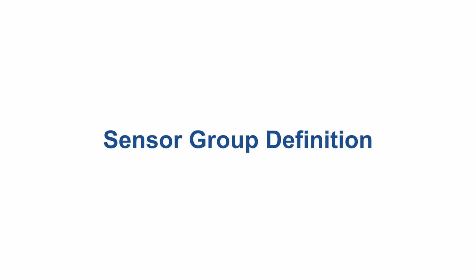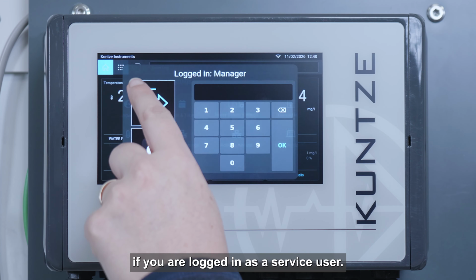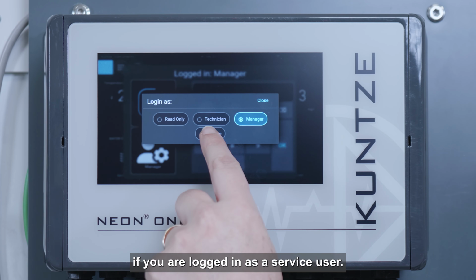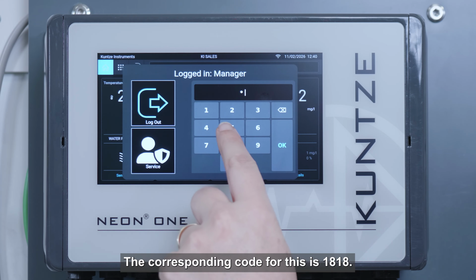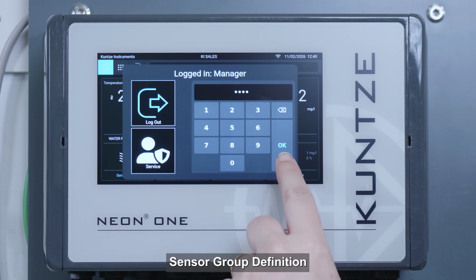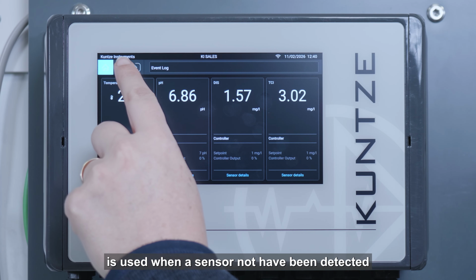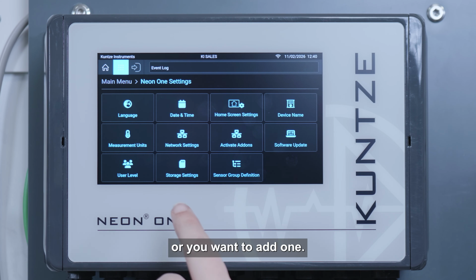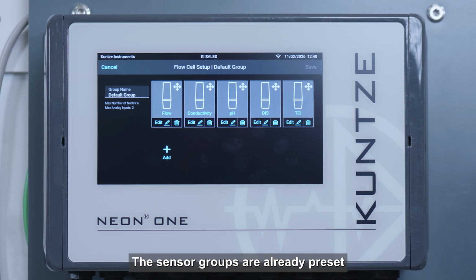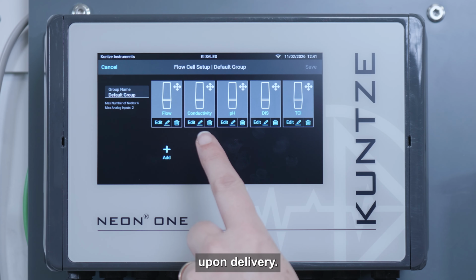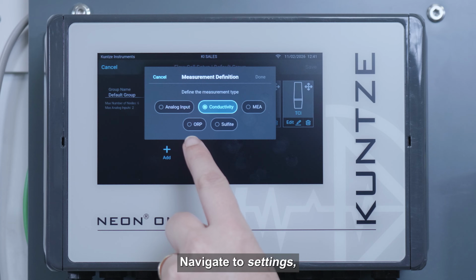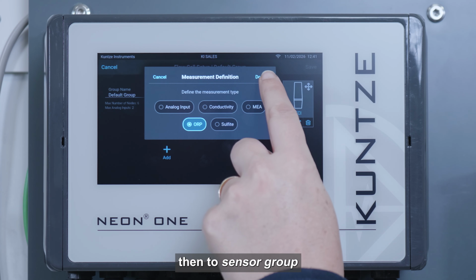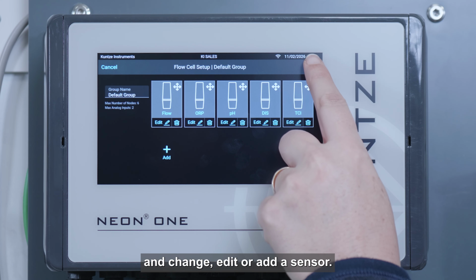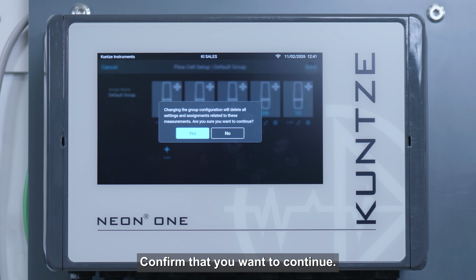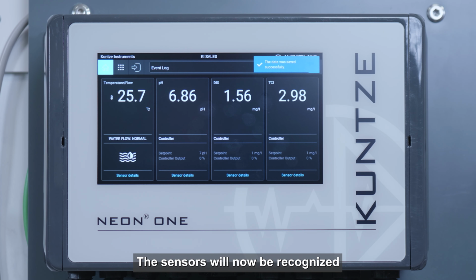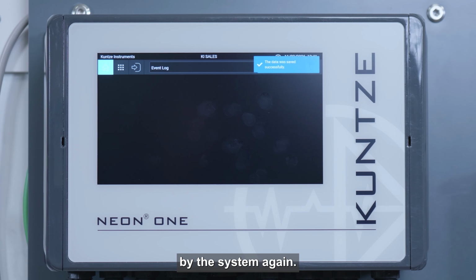Sensor group definition. This is only possible if you are logged in as a service user. The corresponding code for this is 1818. Sensor group definition is used when a sensor has not been detected or you want to add one. The sensor groups are already preset upon delivery. From the main menu, navigate to Settings, then to Sensor Group, and change, edit, or add a sensor. Confirm that you want to continue. The sensors will now be recognized by the system again.